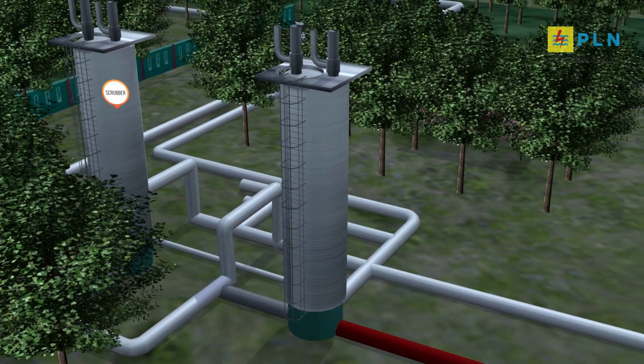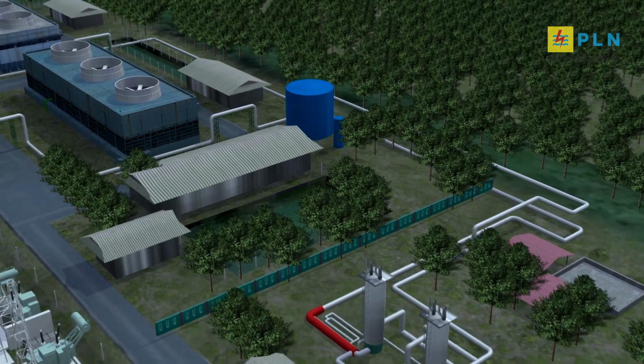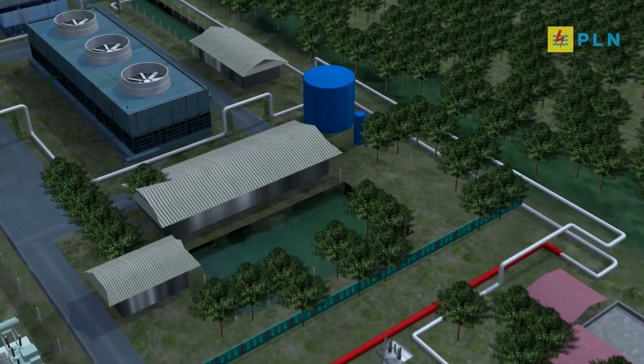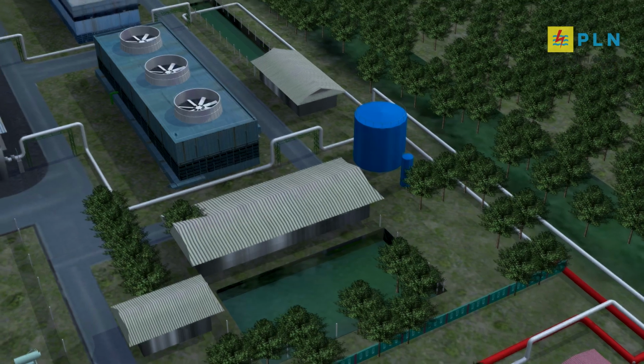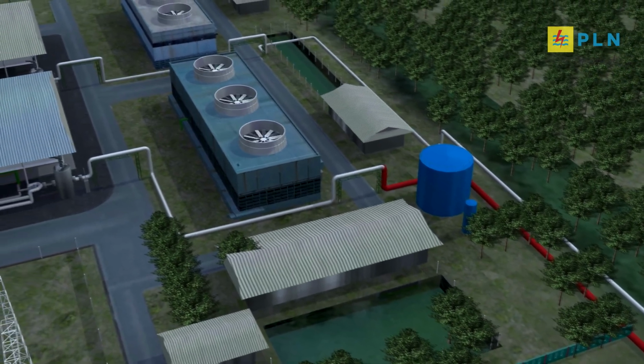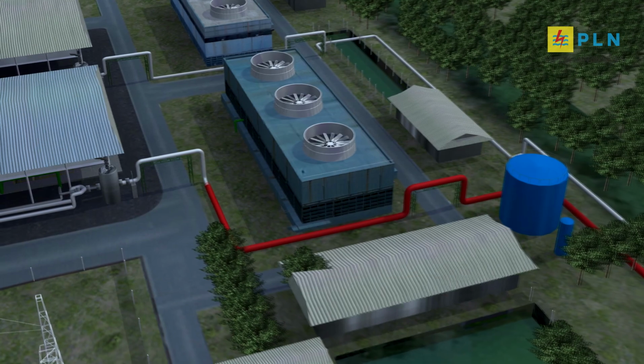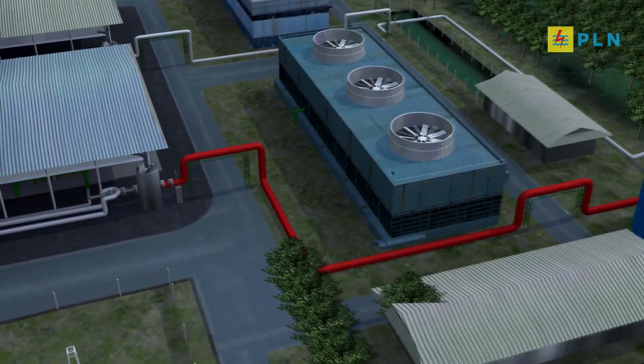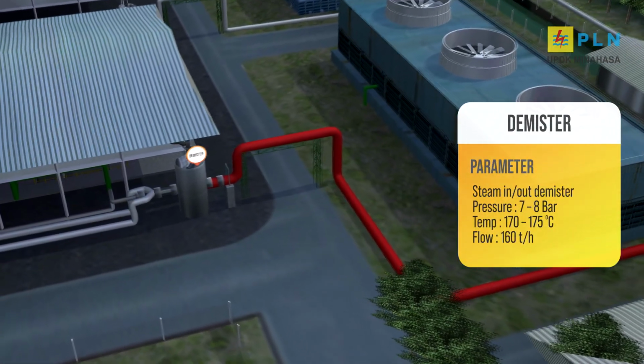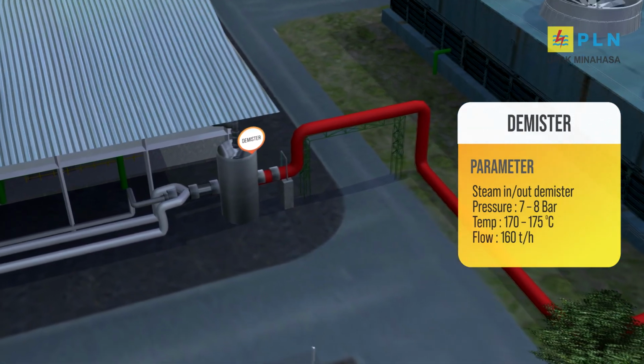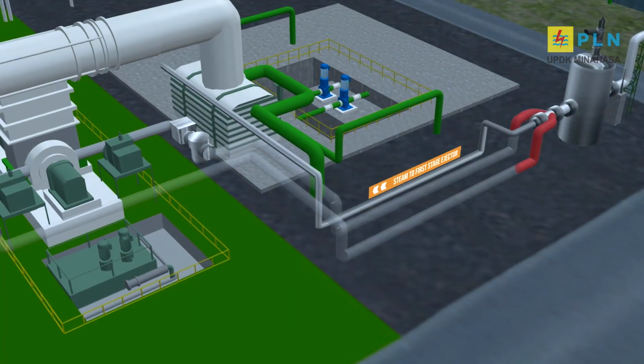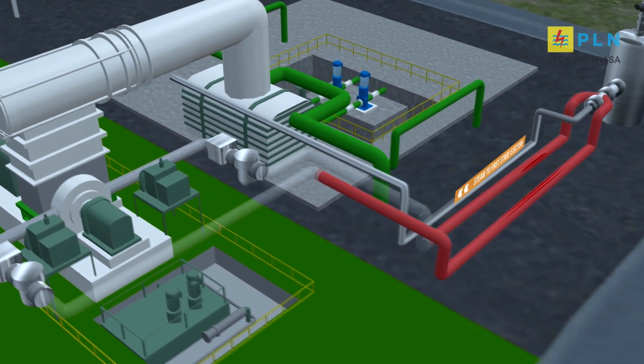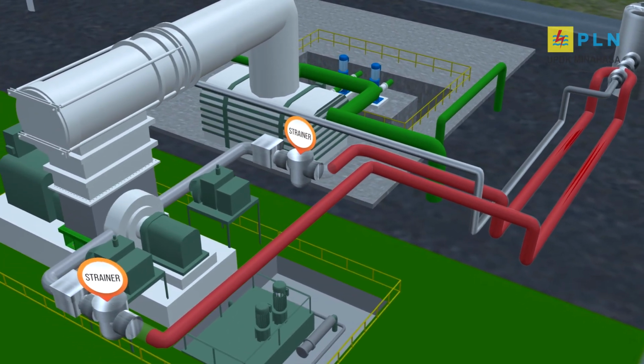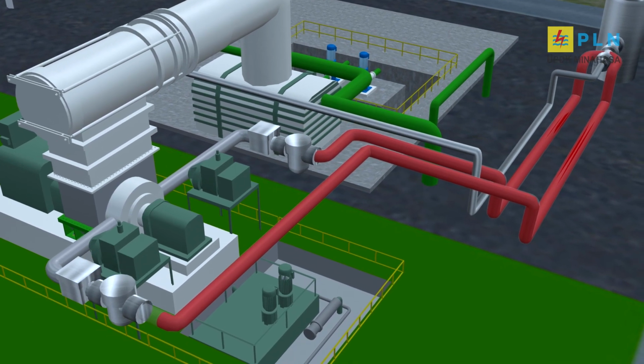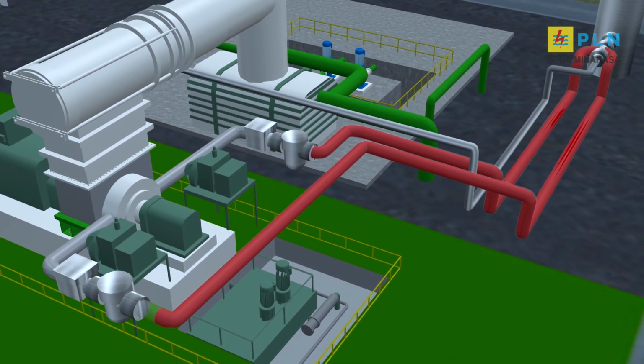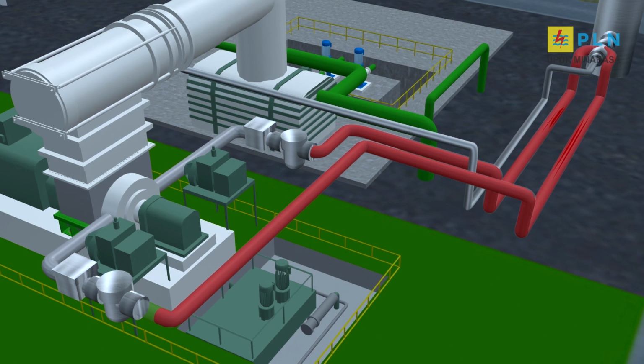Steam from PGE then goes into the demister to separate the particles that still pass from the scrubber. The demister is designed to have an efficiency of 99.99%, so that the pressure that enters the turbine doesn't drop and is in accordance with the turbine control limit. Before entering the turbine, the steam goes through the strainer, which functions as a trap to minimize solid particles formed from the sediment in the demister, so that the steam entering the turbine is clean.